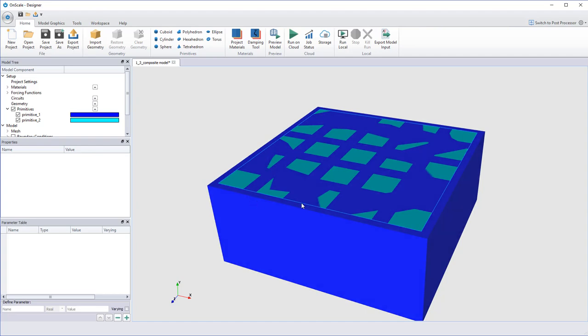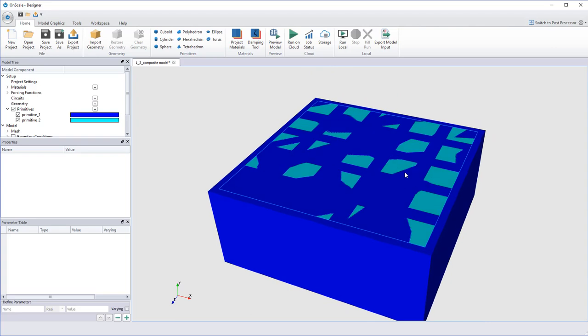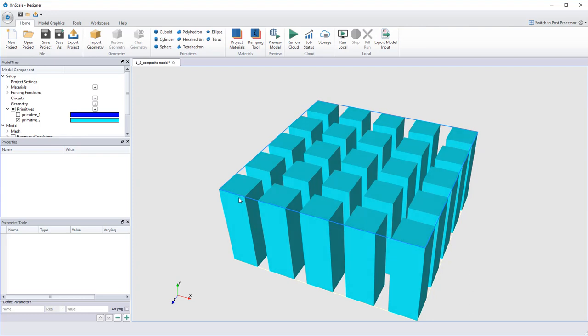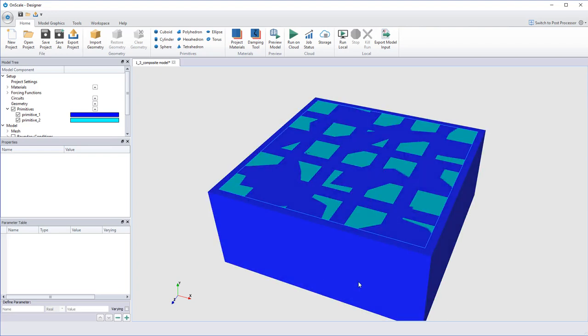So I created this kind of model. This is a piezocomposite array. I have here 25 pillars, which are made of piezo material and which are polarized in the y direction. So they deform under voltage. And in OnScale, you can directly put some electrodes on both sides. You just say what kind of voltage you apply to that, and then it deforms and calculates the mechanical displacement, velocity, and all that. It can calculate that very easily. It's totally coupled.